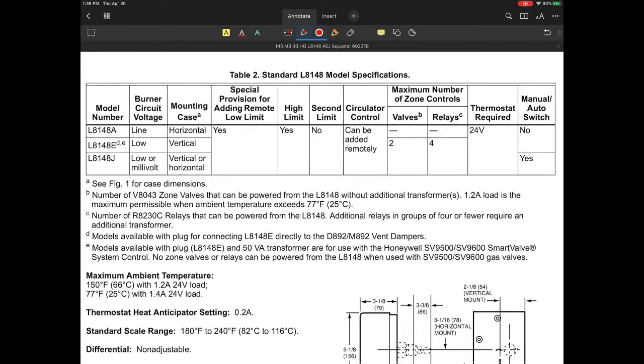All right. I think this little table 2 is a good one to hit on. What I find helpful is, let's say I have an Aquastat, and one of my Aquastats here is the L8148A model. I'm going to find that on the actual unit, usually stamped on the cover or on the inside. Now when I see the model, I want to know what we have for a burner circuit. The burner circuit on that L8148A is an actual line voltage burner circuit. It would be mounted horizontally, which means that in this example the Honeywell logo would be in the horizontal position. It's the only way you can turn that Aquastat to have it look decent.